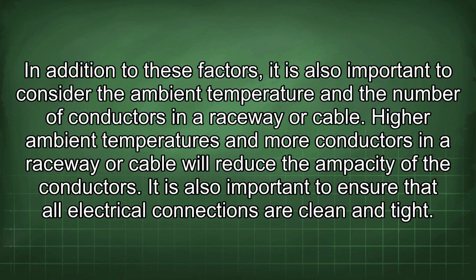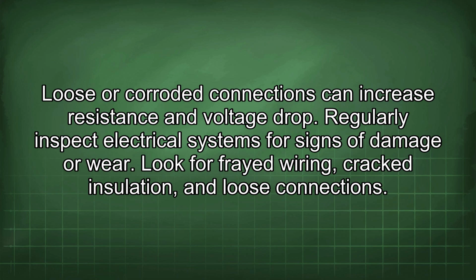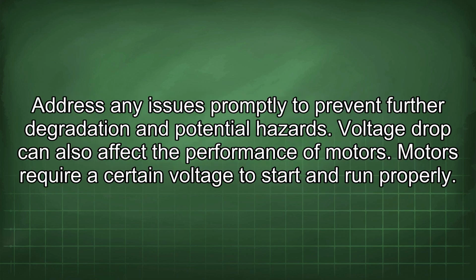Higher ambient temperatures and more conductors in a raceway or cable will reduce the ampacity of the conductors. It is also important to ensure that all electrical connections are clean and tight. Loose or corroded connections can increase resistance and voltage drop. Regularly inspect electrical systems for signs of damage or wear. Look for frayed wiring, cracked insulation, and loose connections. Address any issues promptly to prevent further degradation and potential hazards.